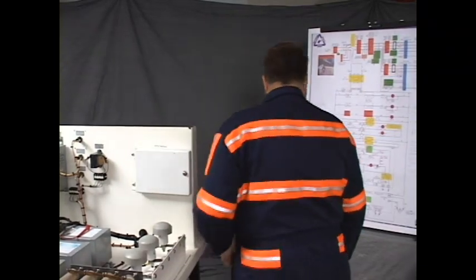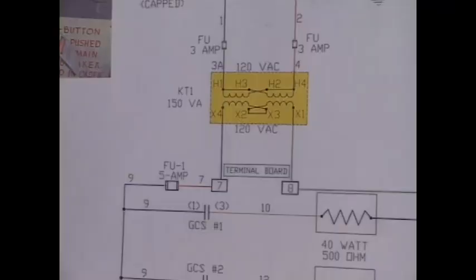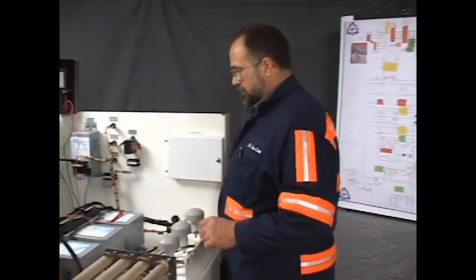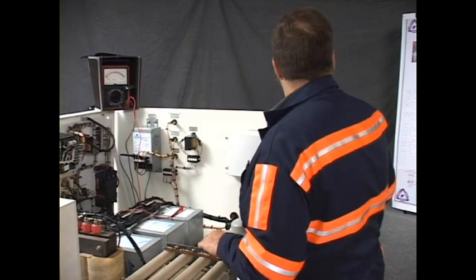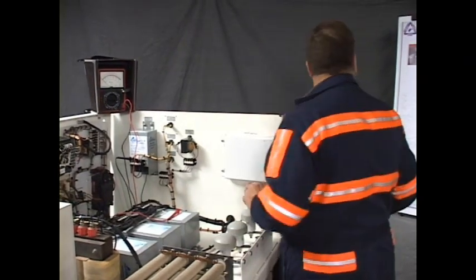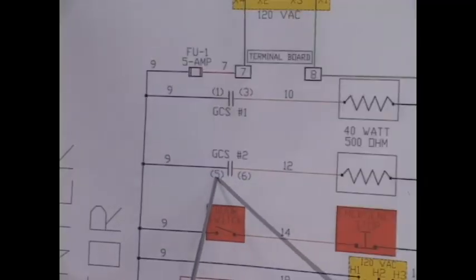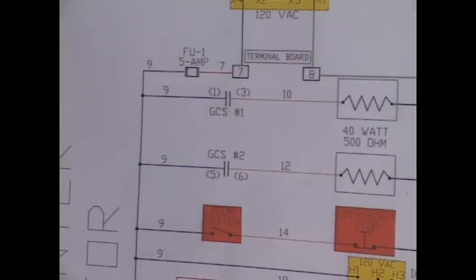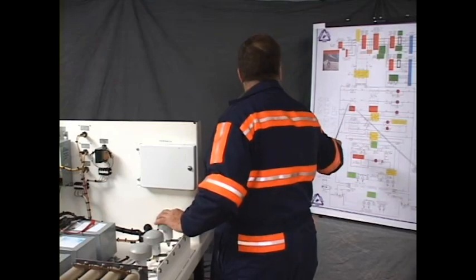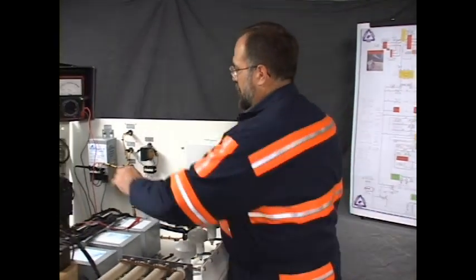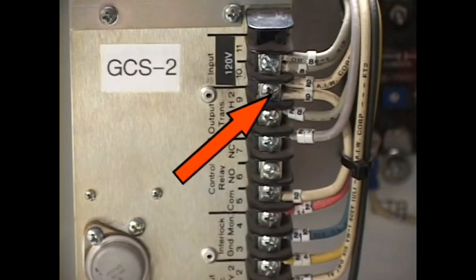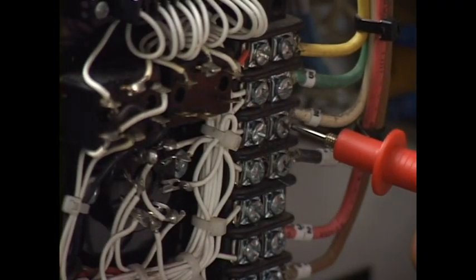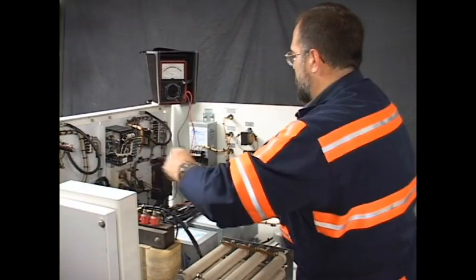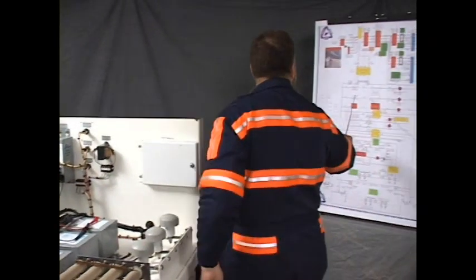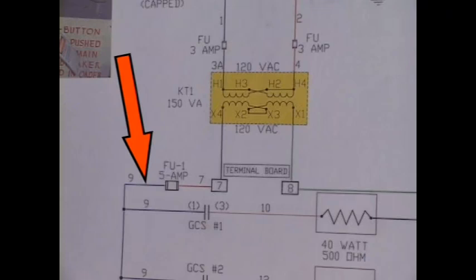As you can see, there's two possible places for it to be broken. Well, let's try to pinpoint that a bit. What I'm going to do is read further into the circuit to the next point shown. GCS 2, terminal 5 has a 9 wire. It's supplied by 9 as well. I'm going to read from 1 to 5. Remove the probe that I have on terminal 7, and using it, read wire number 9 to wire number 9. And we have a good circuit. So that proves that wire 9 is intact from here to here. Our problem must lie here.